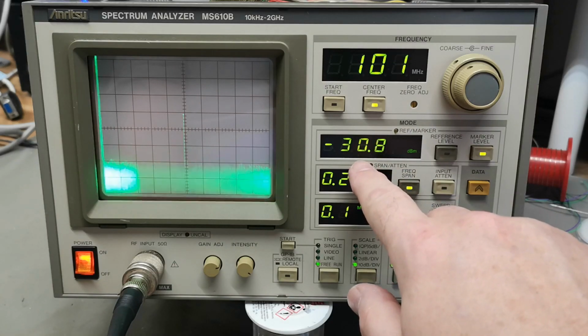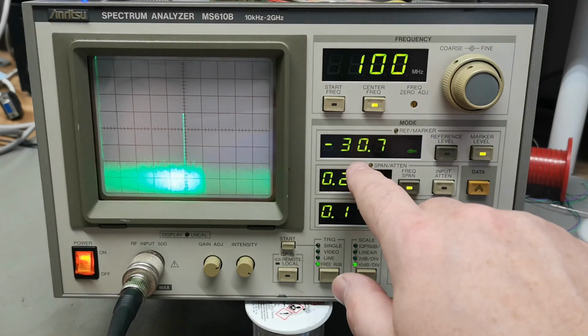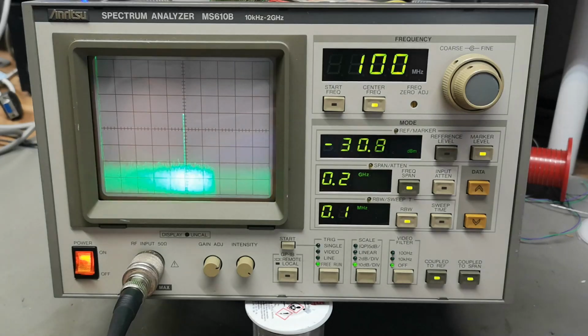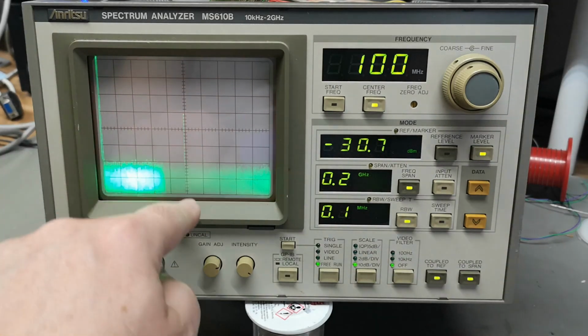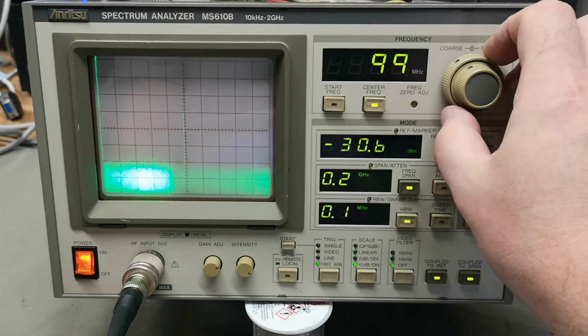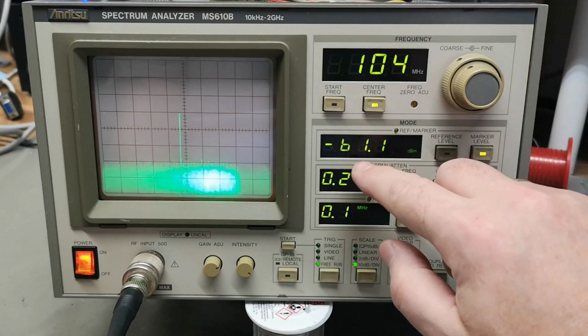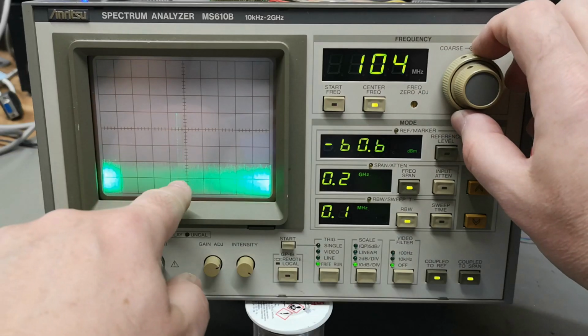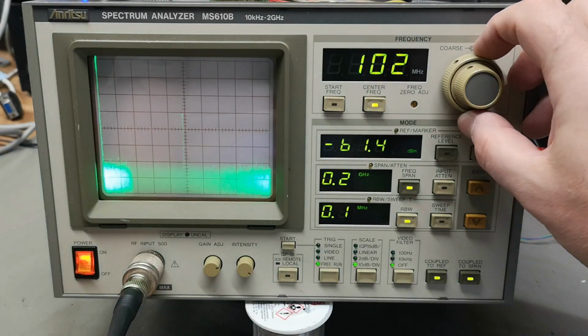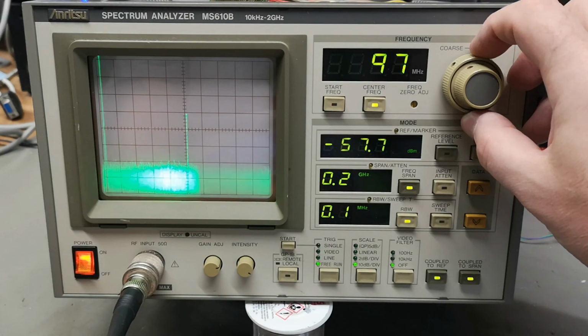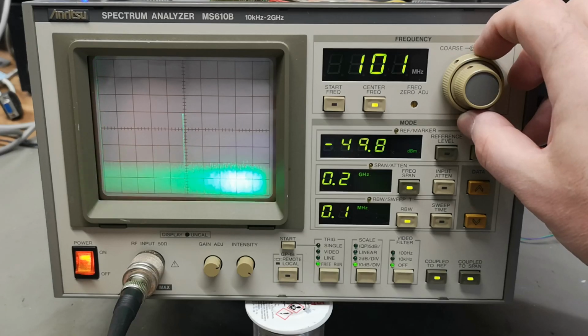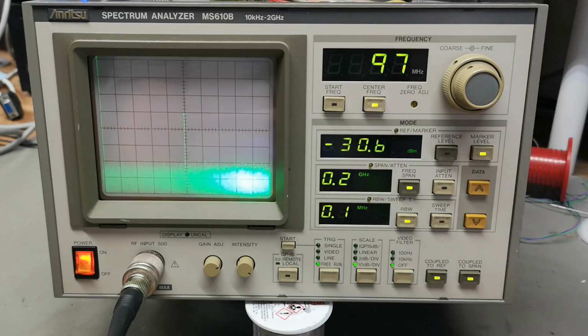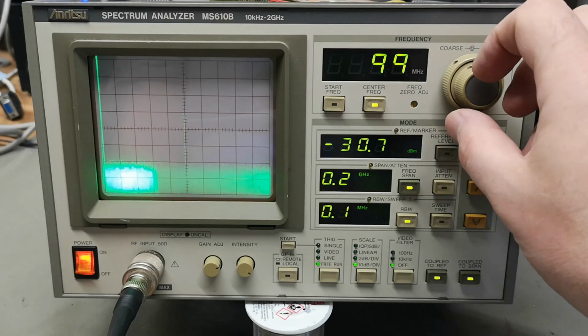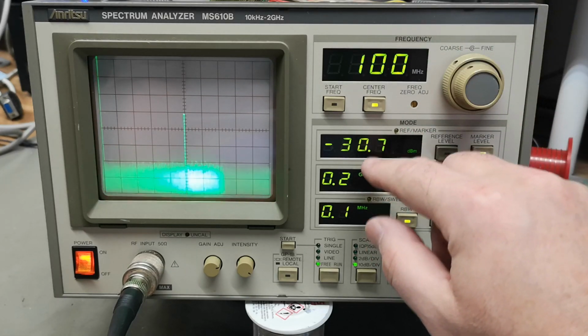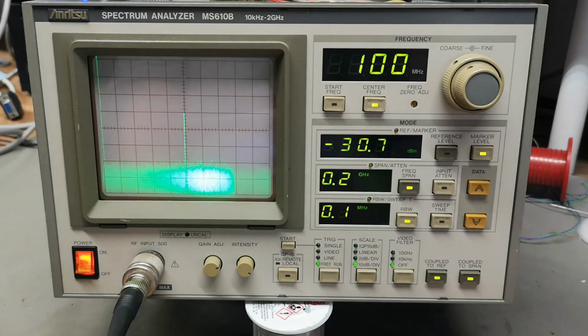And if we go back to marker level, see, here is my power, my minus 30 dBm. That is my input level. And it's only measuring in the middle here. So if I tune, see, the signal goes away, right? So this is my noise floor, and here in the middle, here's my signal. So the idea is you fine tune to the highest level, and then you measure the frequency.